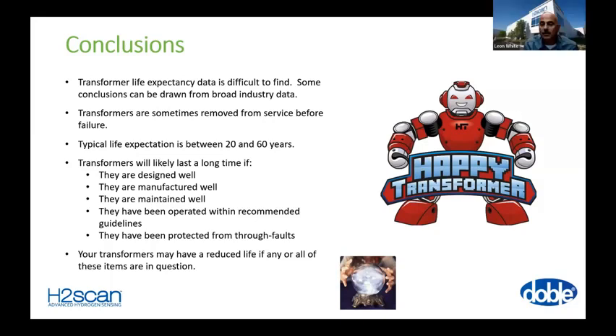Right. It's also important to note, Tony just talked a lot about bushings there. Bushings are a common failure of transformers, and it's important to note that when people monitor the oil or the fluid in the main tank, the bushing can fail regardless of what the oil in the main tank looks like. So bushing monitoring is becoming more and more popular, and as Tony pointed out, there's a lot of reasons for that.